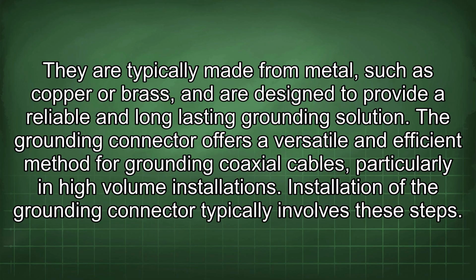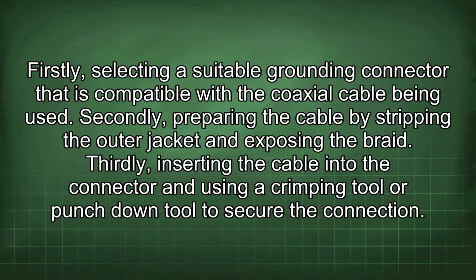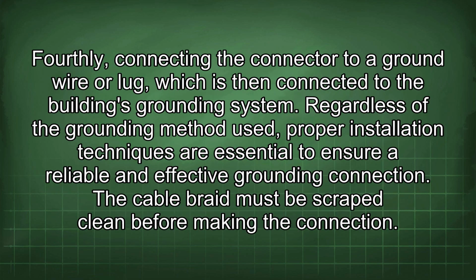Installation of the grounding connector typically involves these steps. Firstly, selecting a suitable grounding connector that is compatible with the coaxial cable being used. Secondly, preparing the cable by stripping the outer jacket and exposing the braid. Thirdly, inserting the cable into the connector and using a crimping tool or punch-down tool to secure the connection. Fourthly, connecting the connector to a ground wire or lug, which is then connected to the building's grounding system.